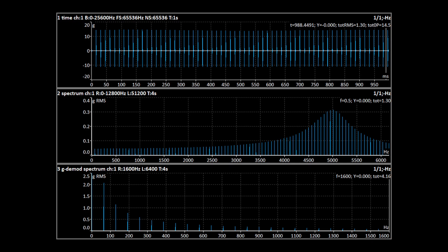Let's see what it looks like. The BPFO is clearly visible in the demodulated spectrum along with its harmonics. We point at the first eight of them in the graph.